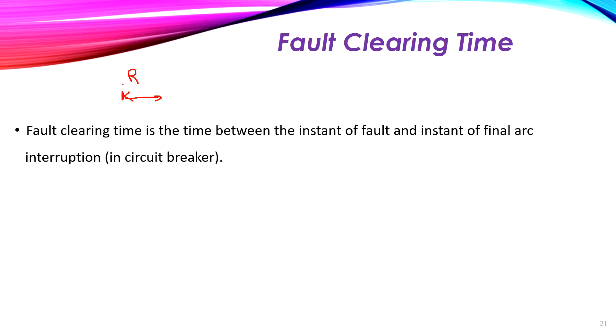After the relay time, we have another time for the circuit breaker when it trips or opens the circuit, including the arc interruption inside it. When a fault occurs, the current transformer steps down the current for the relay. When the current exceeds the pickup value, the relay sends a signal to the circuit breaker to operate.